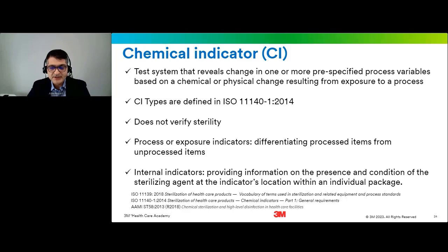Chemical indicator types are defined in ISO 11140 Part 1. Chemical indicators do not verify sterility. Process or exposure indicators are to differentiate processed items from unprocessed items, and that's what they have been designed for. On the other hand, internal chemical indicators provide information on the presence and condition of the sterilizing agent at the indicator's location within an individual package.